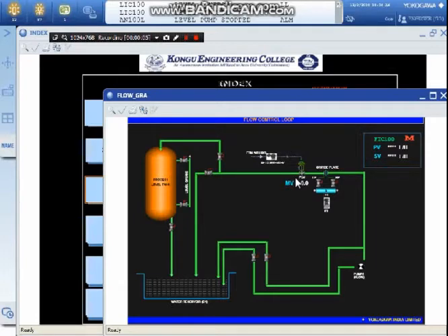Two feeds are taken, and the feeds are connected with the differential pressure transmitter through a three-way manifold valve. From this it is then connected to the DCS. So the flow through this line is measured through this orifice restriction and DPT, and we need to control the flow of this liquid. This can be controlled through this control valve, which will be operating.